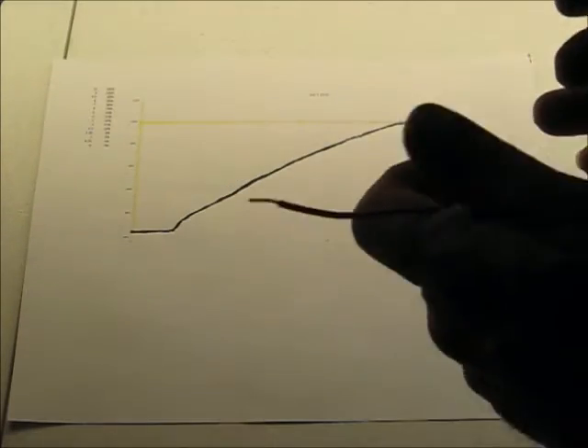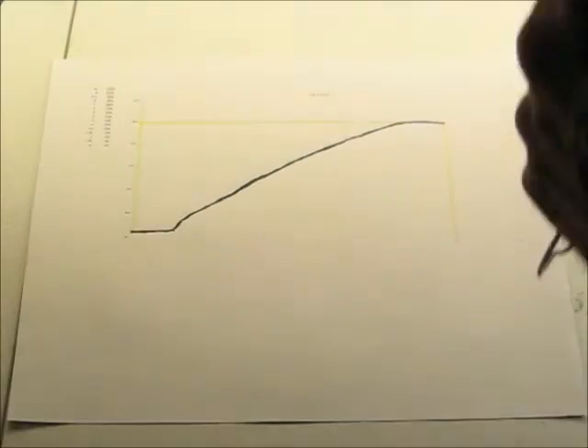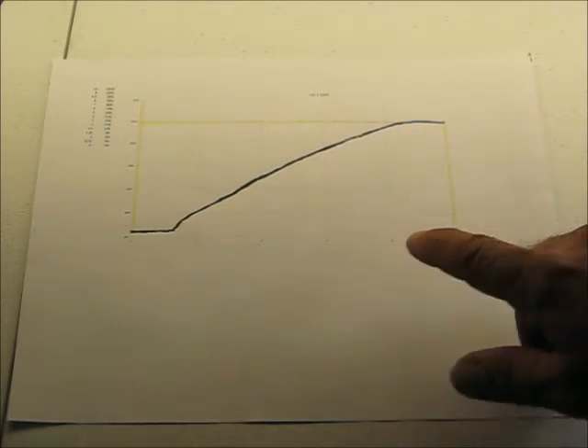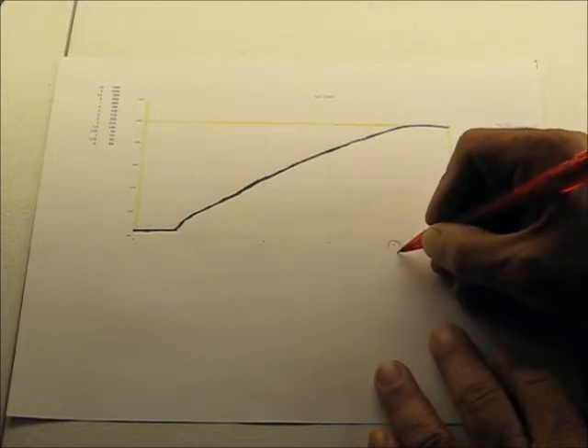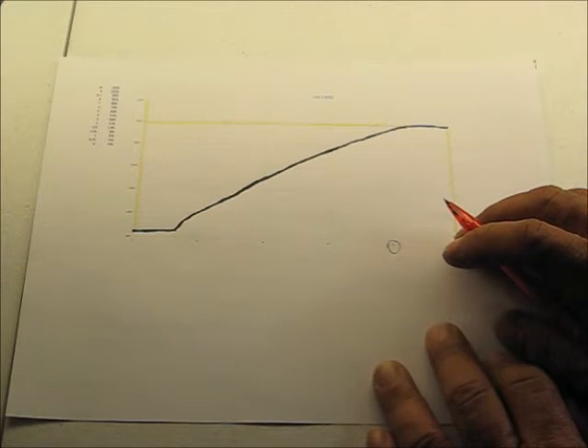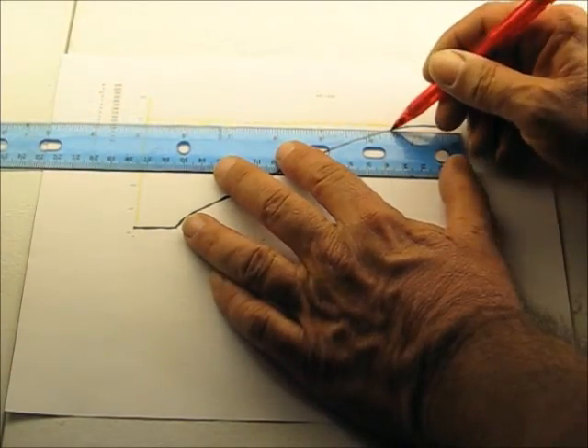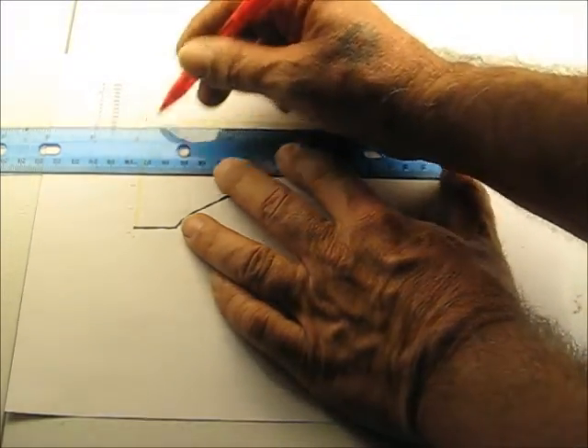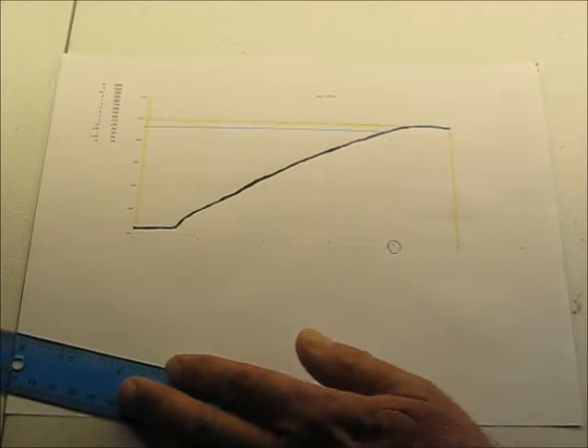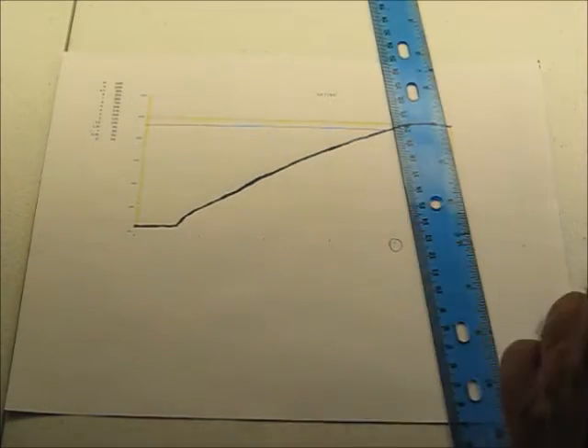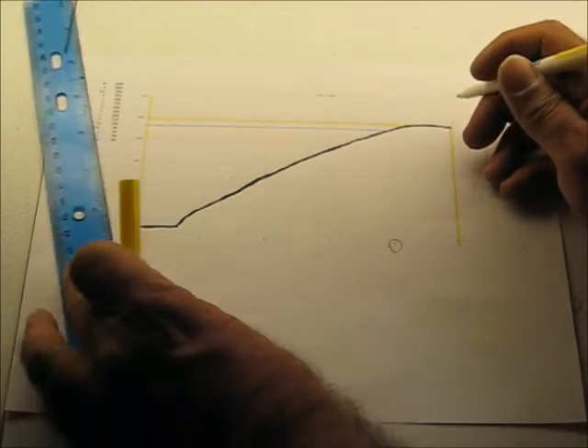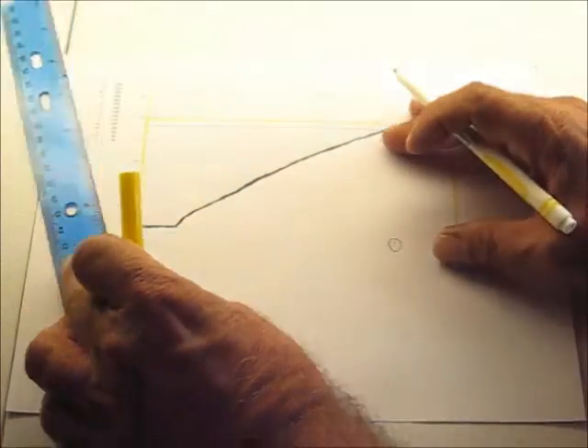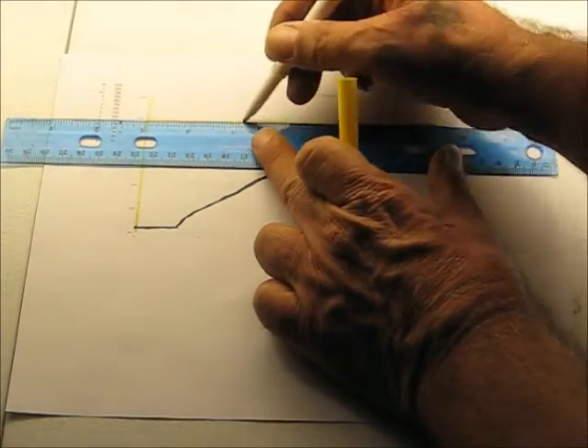Let's examine our response graph for our 0 to 10 volt dimming ballast. First, we think as lighting commissioners that if we put in an 8 volt control voltage output for demand response, we're going to get a 20% reduction in the area on a 0 to 10 volt system. You could not be more wrong. You're way up here at 90-something percent, and you're lucky if you even get those results. This is 100% to 0% of illumination out. And then here we have 0 to 10 volts of command voltage.